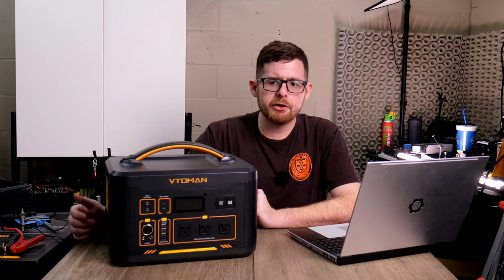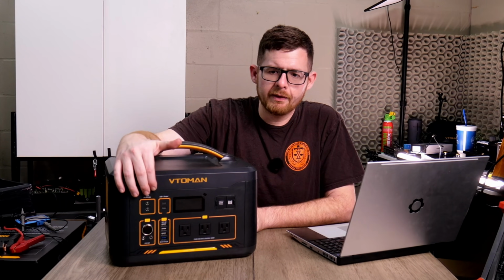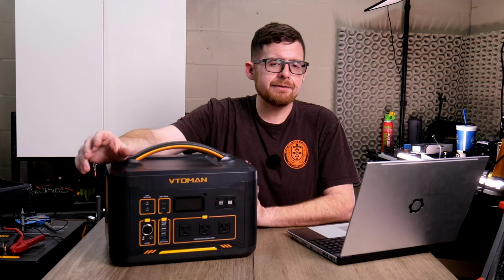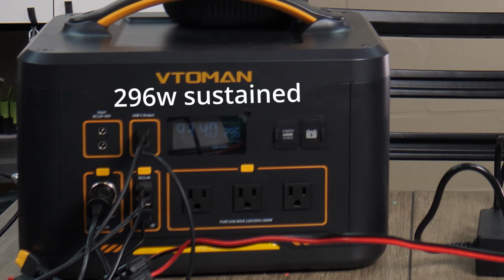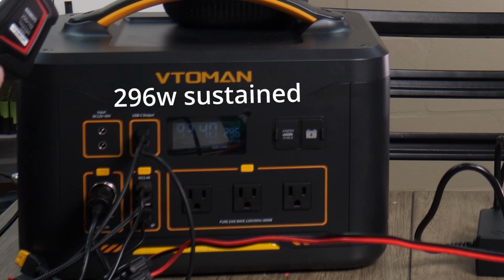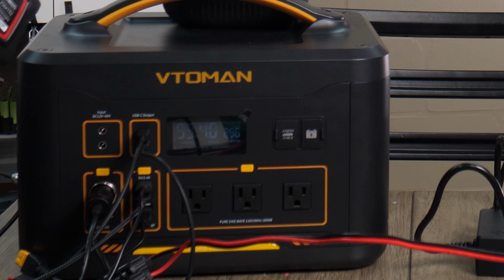The first thing I wanted to do is test the DC output here. The protection they use on that front panel is not temperature based. It is in fact simply wattage based, and it does cut off if you attempt to pull more than 300 watts out of a combined total of these ports.